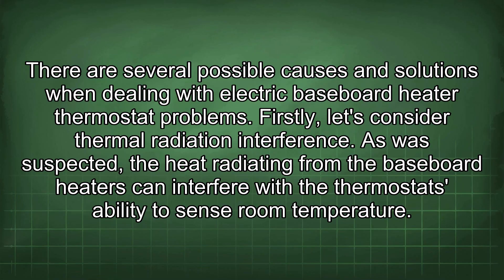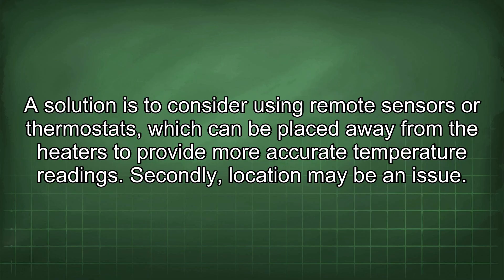There are several possible causes and solutions when dealing with electric baseboard heater thermostat problems. Firstly, let's consider thermal radiation interference. The heat radiating from the baseboard heaters can interfere with the thermostat's ability to sense room temperature. A solution is to consider using remote sensors or thermostats which can be placed away from the heaters to provide more accurate temperature readings.